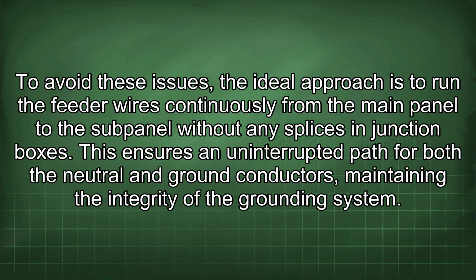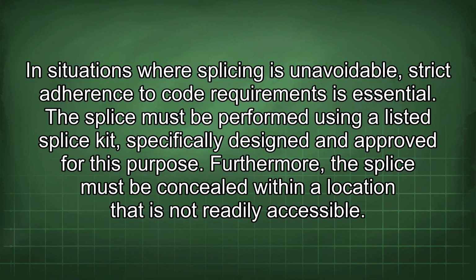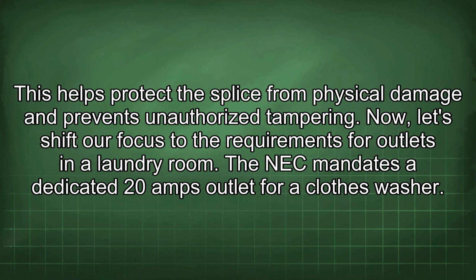To avoid these issues, the ideal approach is to run the feeder wires continuously from the main panel to the subpanel without any splices in junction boxes. This ensures an uninterrupted path for both the neutral and ground conductors, maintaining the integrity of the grounding system. In situations where splicing is unavoidable, strict adherence to code requirements is essential. The splice must be performed using a listed splice kit specifically designed and approved for this purpose. Furthermore, the splice must be concealed within a location that is not readily accessible. This helps protect the splice from physical damage and prevents unauthorized tampering.